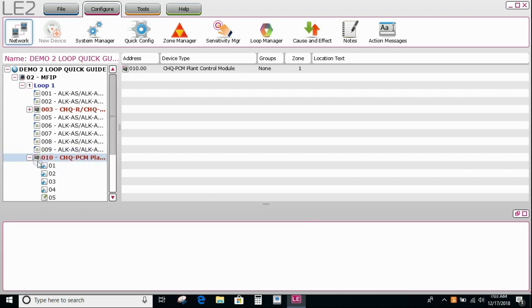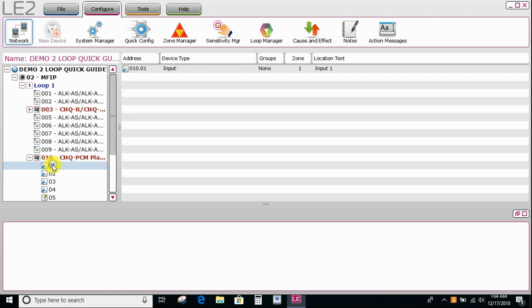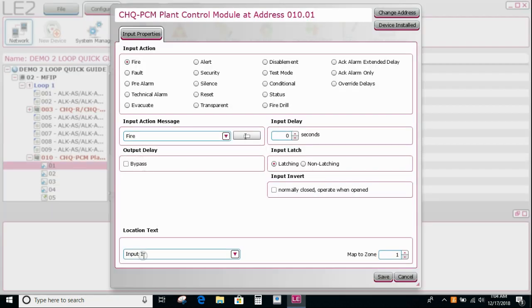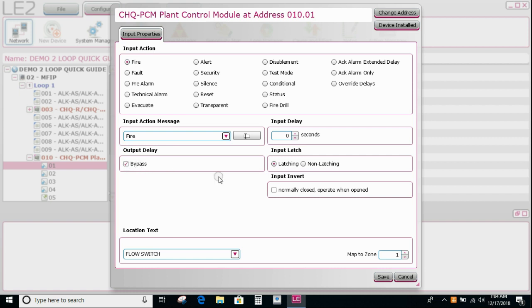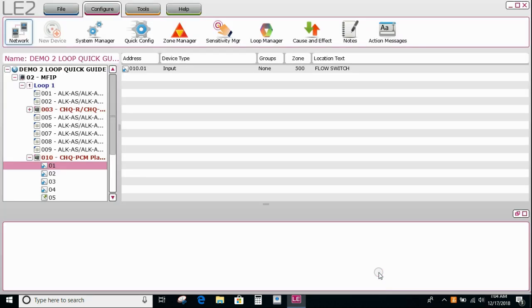So I now need to set up these inputs. So the first one might be a flow switch, which is a fire type event. So make sure it's fire. It's going to bypass any output delays. It will be latching typically. And then you'd set your zoning. If there's any zoning, maybe they're all going to go into, all the flow switches into 500, something like that. So you save.